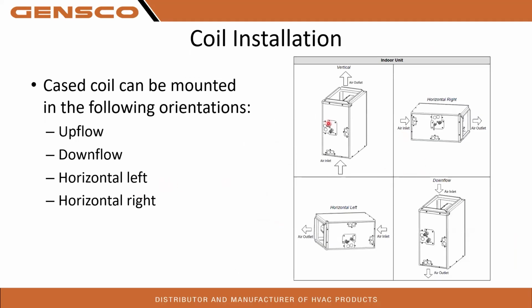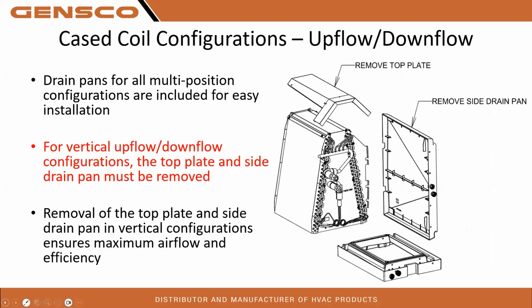And again, this slide here is showing the different positions. You can go upflow, downflow, horizontal right, horizontal left, depending on your needs for your design. And here's a better picture of the coil with the drain pan and the top plate that I was talking about. Again, if you're going in an upflow or downflow, this drain pan and this top plate will need to be removed. That will give you better static pressure readings and create a little better airflow for you and not give you airflow problems.